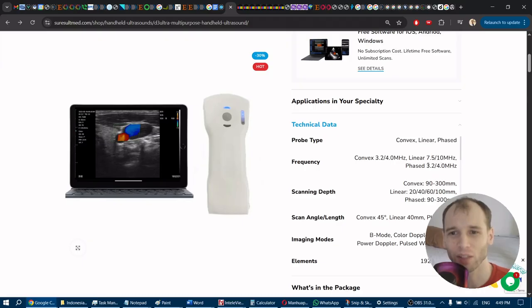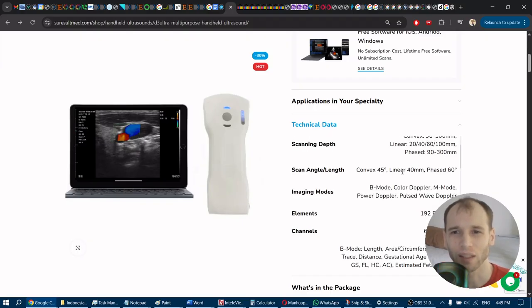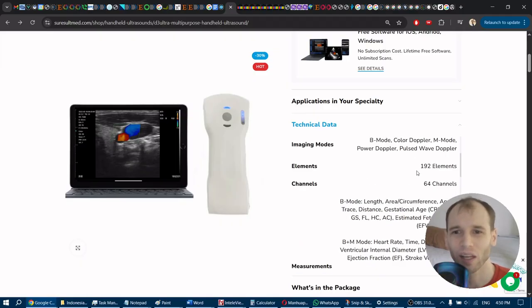And in terms of the frequencies, they do have a typo here. The convex, it's 3.2 to, I think, 5 megahertz are the two settings. Linear is 7.5 or 10, and I think they have it correct for the phased array. And scanning depth, linear, it is 40 millimeters, whereas my Clarius is 50. And I do like the Clarius because it has a little bit more width to the image, but you get what you get. And of course, this has all the B mode, color Doppler, M mode, power Doppler, pulse wave Doppler, has all the modes you could want. As I mentioned, 192 elements, 64 channels.